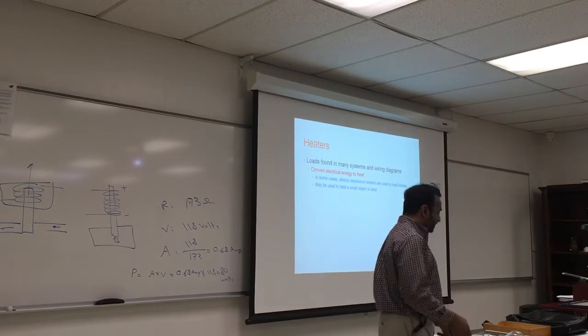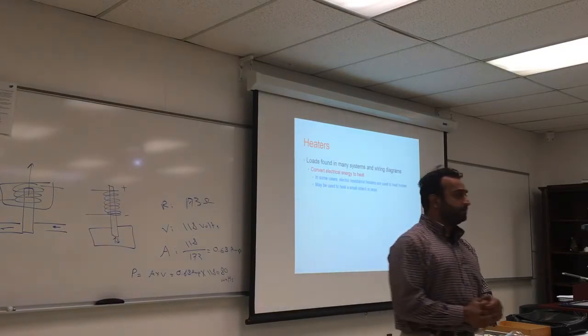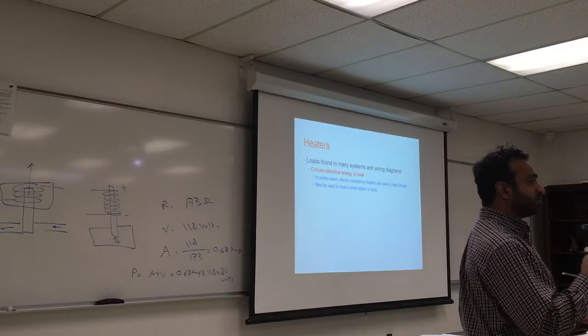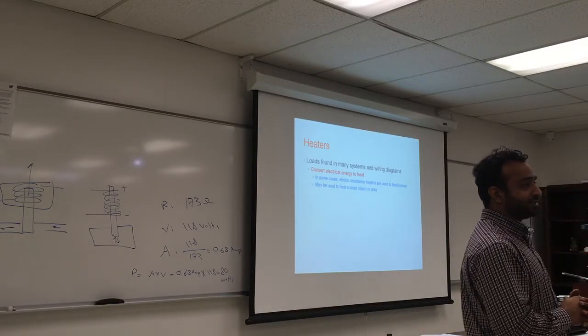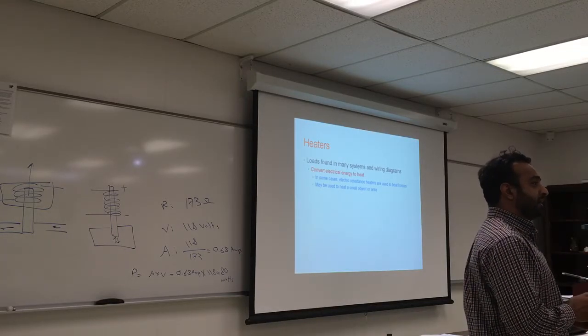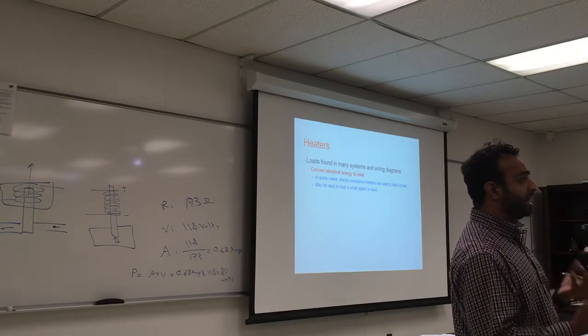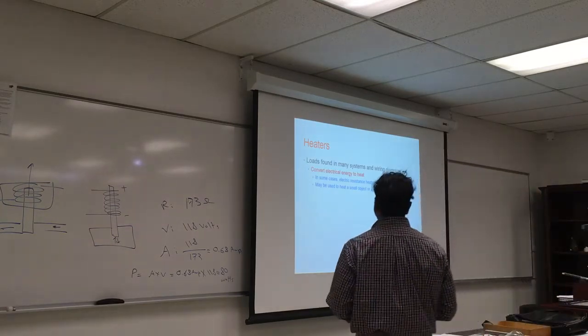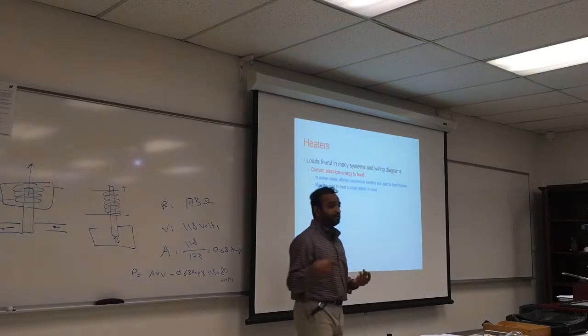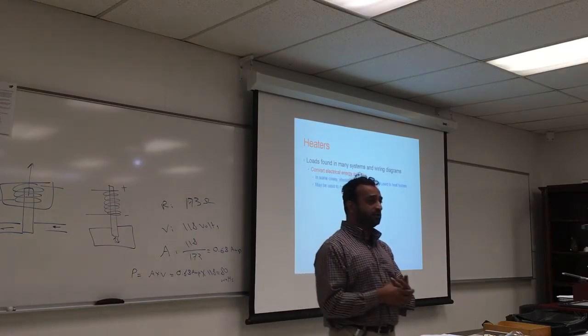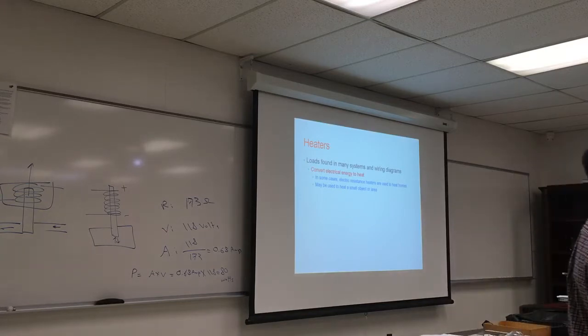Heaters. We talked about them before: small coils made out of sometimes tungsten carbide, or another kind of material that has high resistance. You run current through them and they start heating. You might find them in ice makers and freezers as a defrost cycle. They generate heat on location. You turn that on and it heats the coil, and the coil melts the ice for defrost.